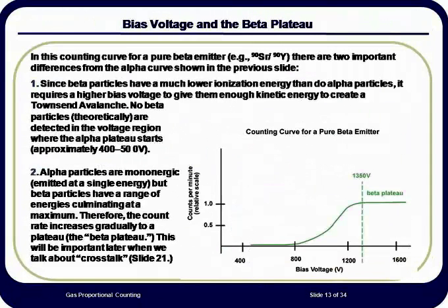Beta particles ionize much fewer atoms per linear path length than do alpha particles. Thus, in order to accumulate enough collected charge for a measurable pulse, the amplification of the original beta particle ionizations needs to be more significant than for alpha particles. Thus, there is a very limited beta contribution to the pulse size in the alpha region.